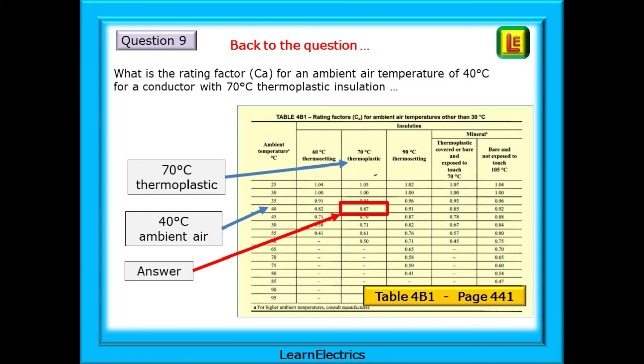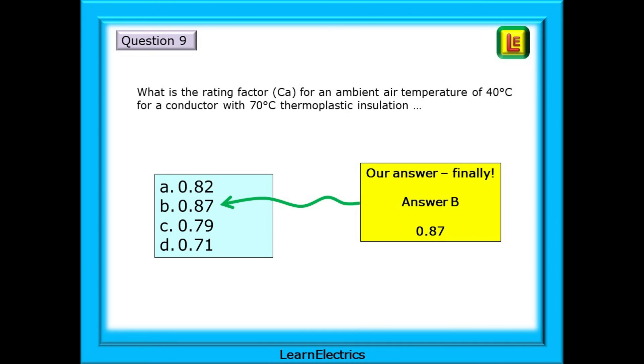Back to the question then. What is the rating factor CA for an ambient air temperature of 40 degrees Celsius for a conductor with 70 degrees Celsius thermoplastic insulation? and we now know that Table 4B1 is on page 441. Follow the clues in the question. 70 degree thermoplastic narrows the search to just one column. Find 40 degrees Celsius on the left to find the correct row. Where the column and row meet is the answer, a rating factor of 0.87. The answer, finally, is answer B 0.87. If you still haven't updated your book, do so now. You may need that information in the exam.